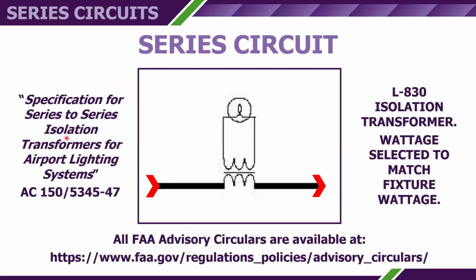Let's get a little better view of it here. The advisory circular for manufacturing isolation transformers is 150/5345-47. They're called L-830 isolation transformers, and L-830 is for our 60 cycle units. You want to make sure that when you purchase LED fixtures, your isolation transformers match the wattage of your fixture. You get the maximum energy efficiency by having a properly sized L-830 isolation transformer. If they're oversized, they'll still work, but you'll end up wasting a little more energy.